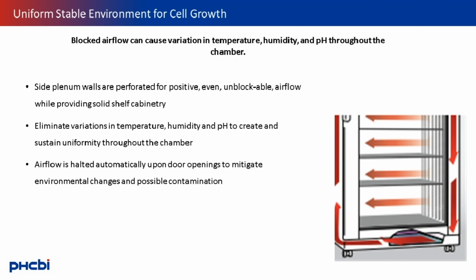A uniform, stable incubator environment can be achieved through a combination of construction and design. Perforated side plenum walls create a positive, even, unblockable airflow, while horizontal airflow allows for full use of solid shelves, which allows for added insulation benefits that I'll discuss later. And upon door openings, airflow is halted. This prevents an excess of air exchange between the outer and the inner environments, thus guarding against chamber variations and contamination entry. It's important that the incubator environment maintain a uniform, even airflow. Variations in temperature, humidity, or CO2 can create inconsistencies in cell homogeneity, quality, and viability.